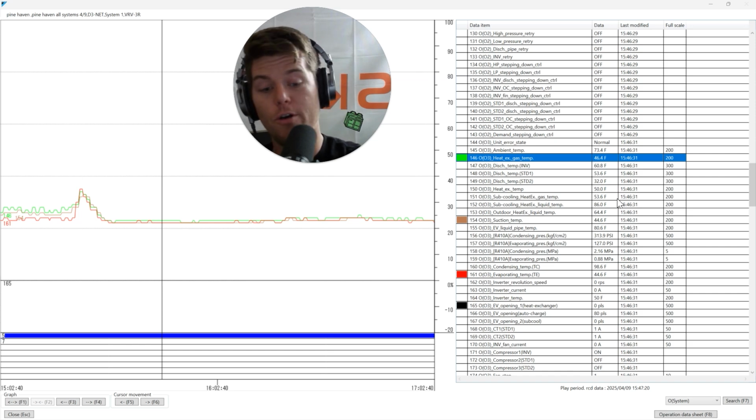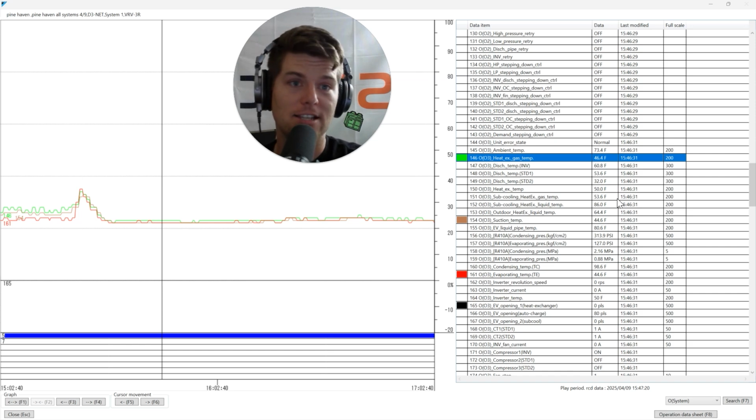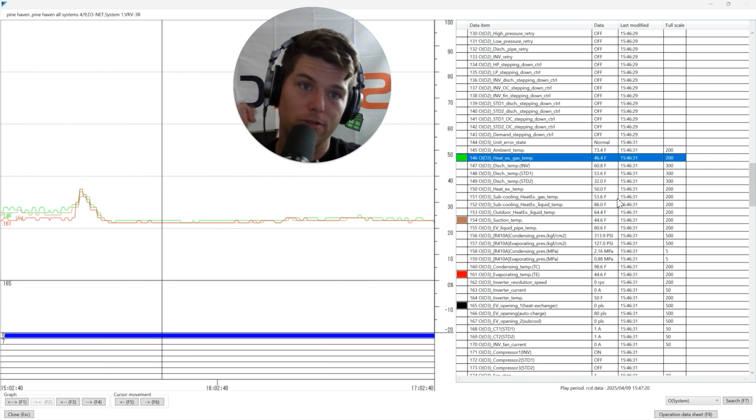That's it. And you can even go a step further, and you can shut the hot gas line that's actually shared to that module. And what will happen is anytime the unit tries to send hot gas directly to that module to do some kind of rotational thing, the high pressure will spike. It'll go into restart standby, and it will never use that module again. Ask me how I know, because I've done it.